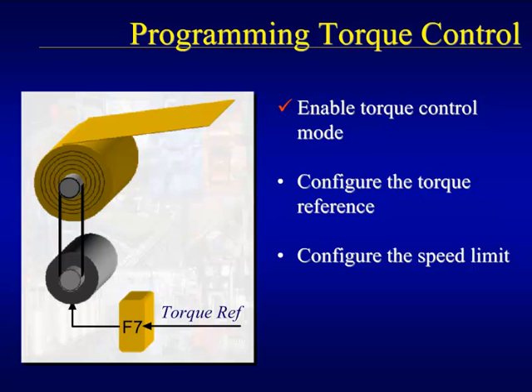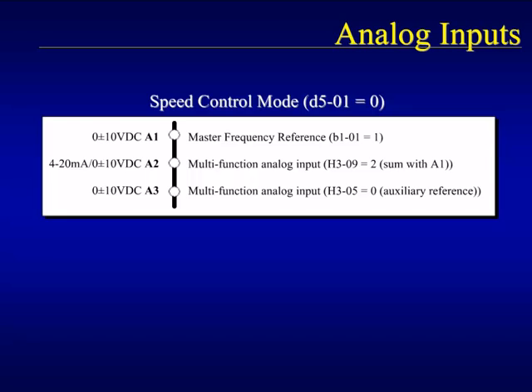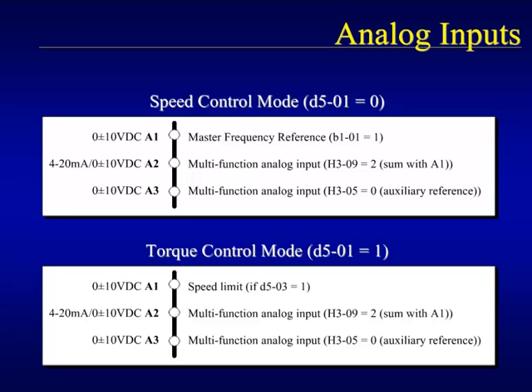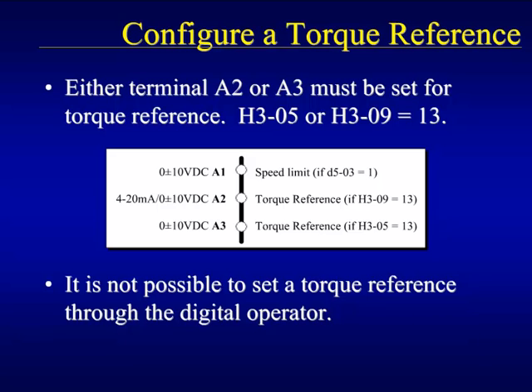Now that Torque Control is enabled, a torque reference must be configured so the drive knows how much torque the motor should output. Let's look at the analog inputs during speed control. The factory default settings for the analog inputs show terminal A1 as the master reference. Configuring the drive for Torque Control changes the function of terminal A1 from master speed reference to the speed limit function, whereas terminals A2 and A3 retain the same functions when in speed control. Either terminal A2 or A3 must have its function changed so the terminal becomes the torque reference. Setting one of those terminals for torque reference is accomplished by setting the respective terminal function selection parameter to setting 13. If a 4 to 20 milliamp signal is to be used for the torque reference, terminal A2 must be used as the torque reference terminal.